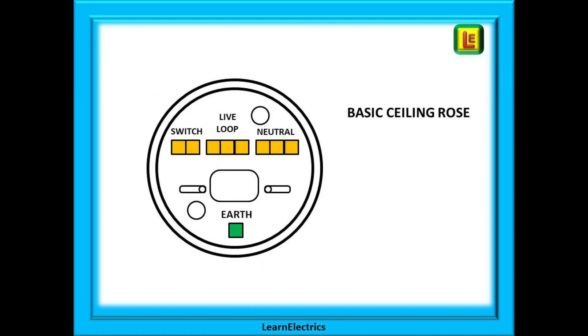Let us move on now and see where we connect the wires in the ceiling rose. And here is our basic ceiling rose. The twin and earth loop cable marked L here comes in from the consumer unit. The brown wire goes to any one of the holes in the loop block.